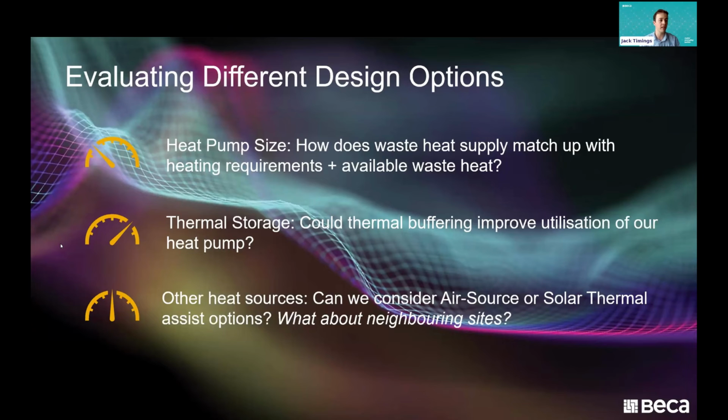And what that modeling exercise showed is that we reached a kind of critical point in which increasing the size of the heat pump, which is more capital spend, actually didn't deliver us very much additional gas offset or carbon reduction opportunities. So doing that exercise identified capacity that we didn't have to install, capital that we didn't have to spend, which was a good result for the project.